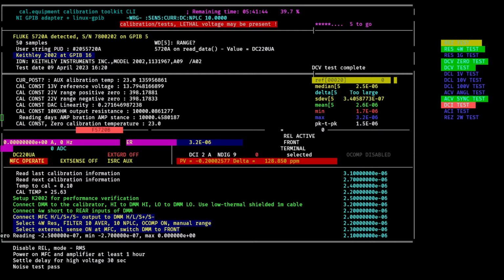So that is, I believe right now, the 2 amp point, 2 amp range, and 0 current point, then 1 amp, 2 amps, and negative 1 amp, and negative 2 amps. So the full run for Keithley 2002 takes about 9 to 10 hours, and this is a calibration for all the ranges and functions you see on the list on the right. The ones marked green already completed, and right now I have DC current test running. Next will be AC current, then resistor 2-wire test, and then the report will be generated to calculate all the uncertainties and pass-fail specs.